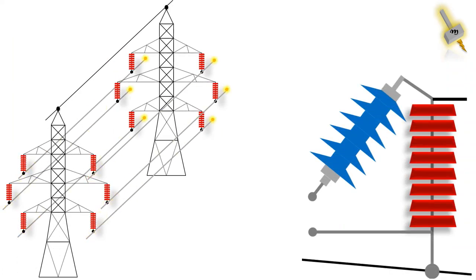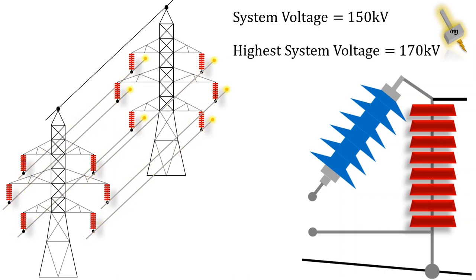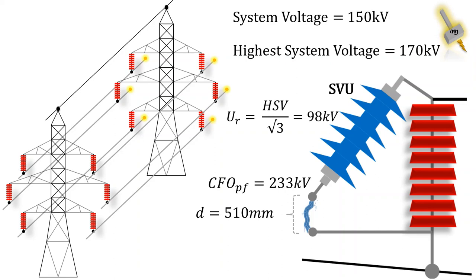Now let's see an example. Let's take system voltage of 150 kV. It will have highest system voltage of 170 kV. So the rated voltage of the SVU will be 98 kV. The critical flashover voltage at power frequency level will be 233 kV. For that, the minimum spark gap distance will be 510 mm.